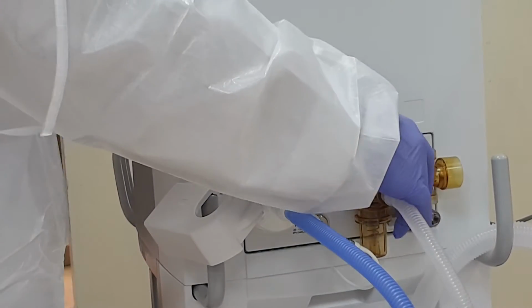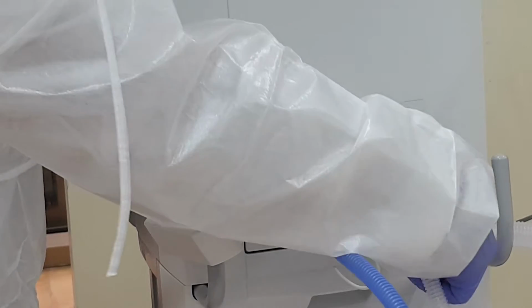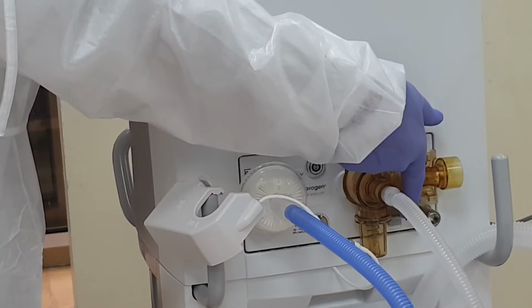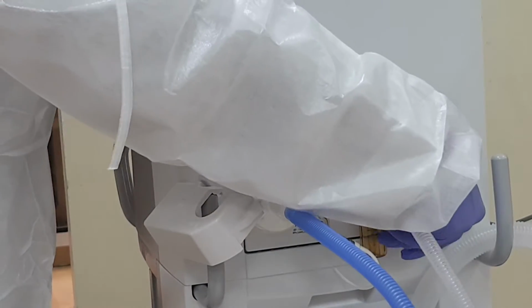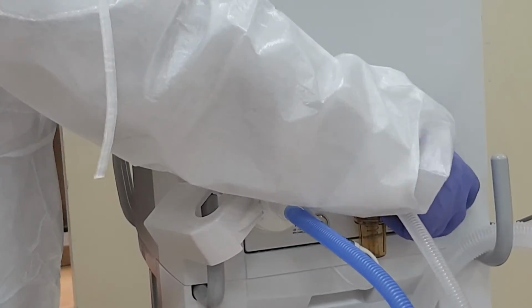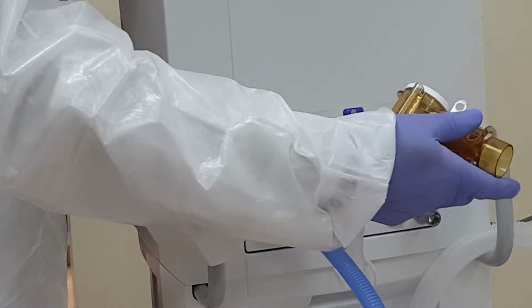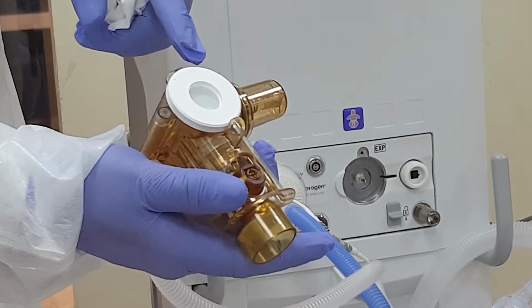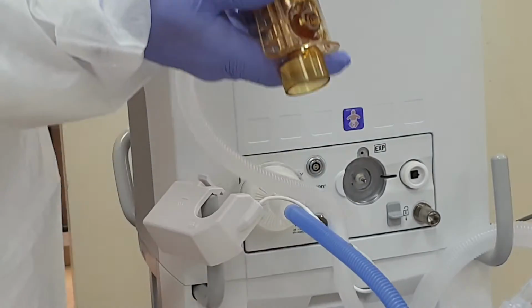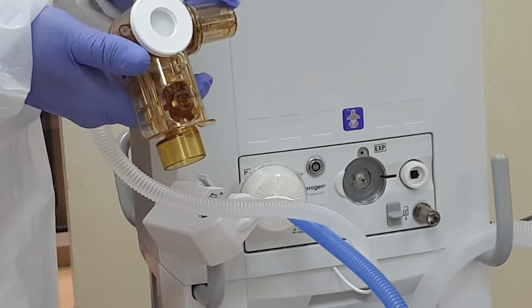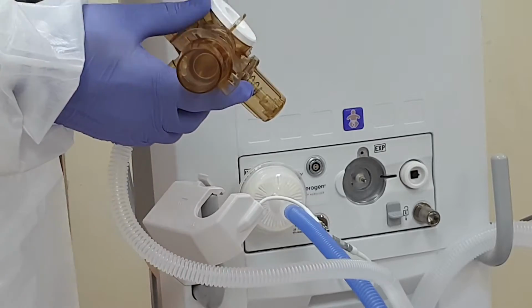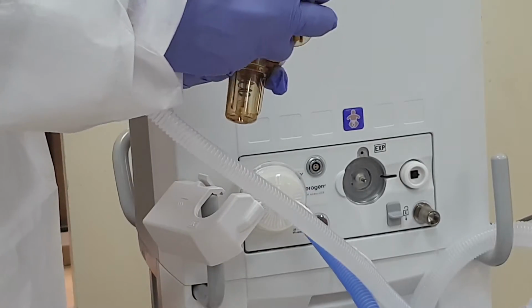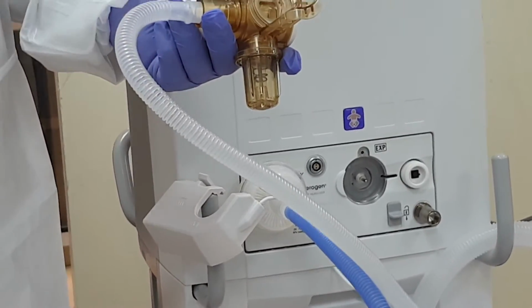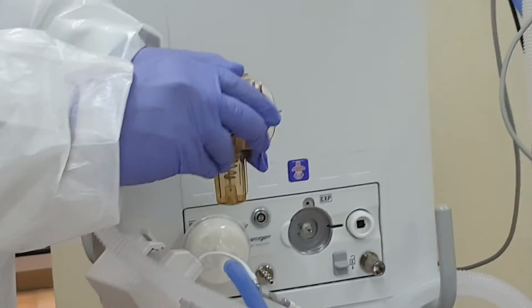If you want to replace the whole expiratory port, there is a small tab down here, if you can see. If you push it down and you can tilt it, the whole thing is out. And this is, by the way, the diaphragm, basically. This is the water trap, and as I showed you, this is the flow sensor.